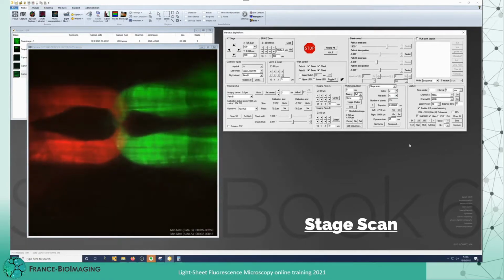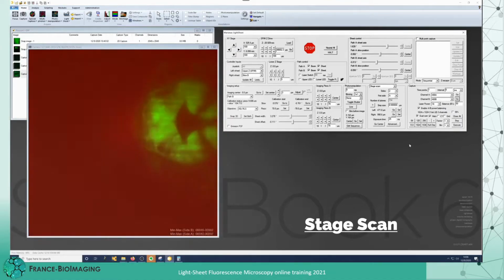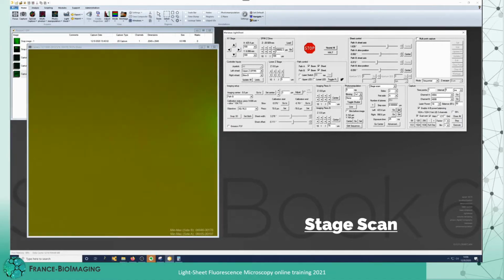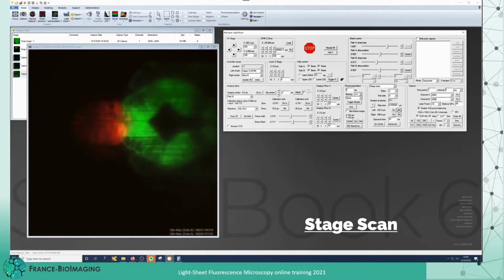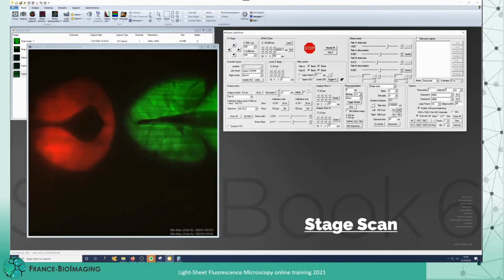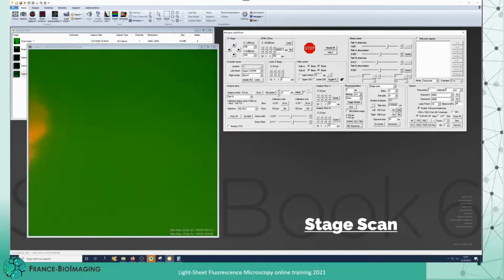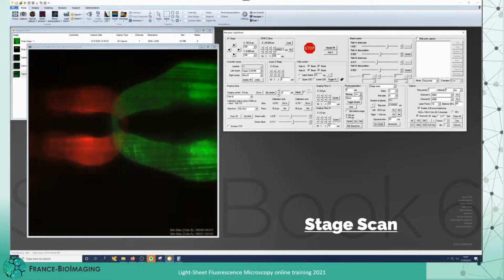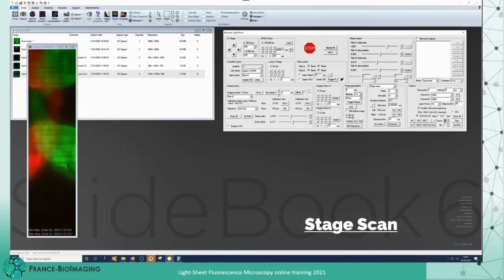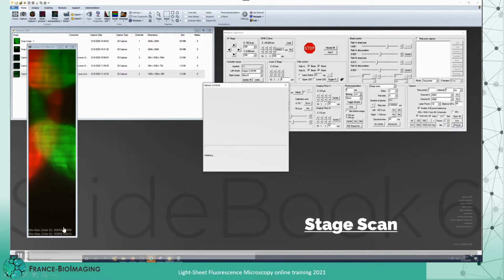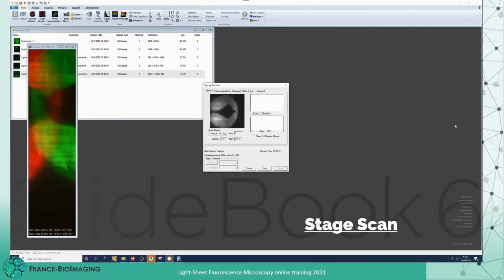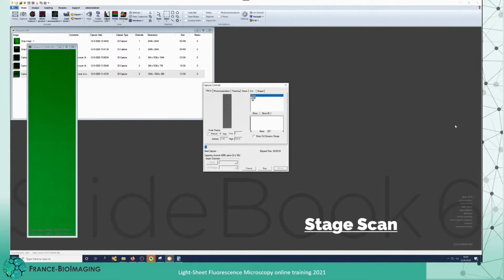Moving all the way to the left-hand side, set this position, and then go all the way across to the furthest position on the right. We can then check the central position for signal adjustments if necessary. As the sample is going through fixed light sheets, we can crop the sensor size even further in order to avoid redundant data. As before, we are now recording in real time a volume of 680 by 163 by 30 micron. This should take less than a minute and benefits from the good fluorescent signal coming from the sample, allowing us to work at 25 millisecond exposure time.